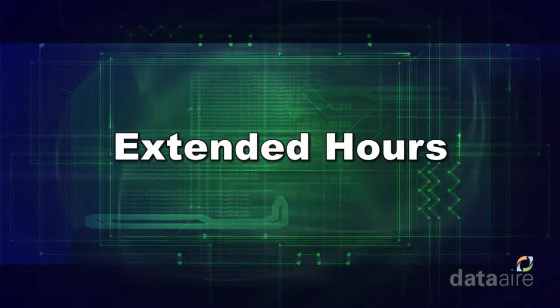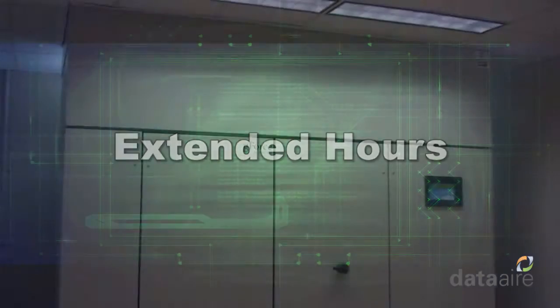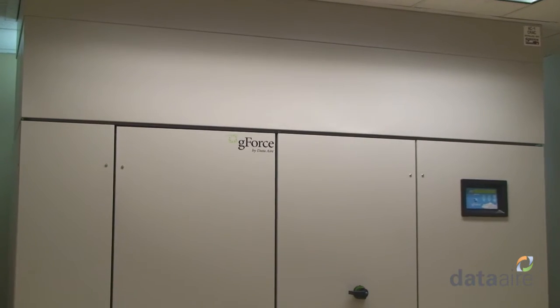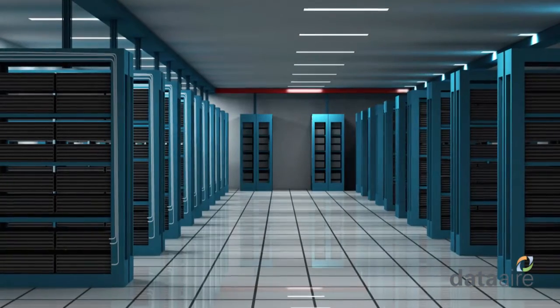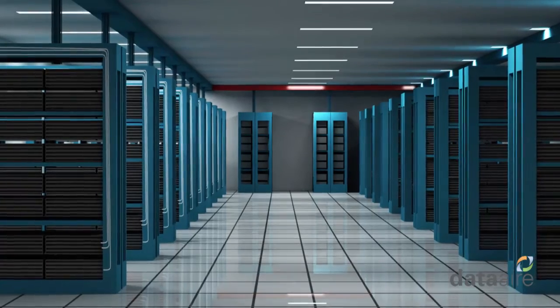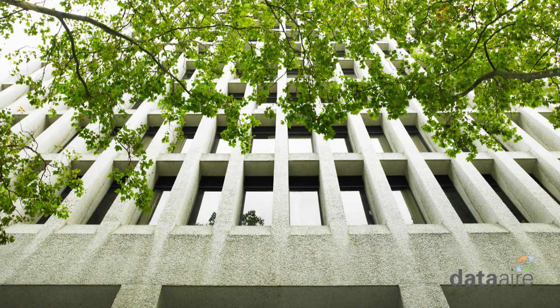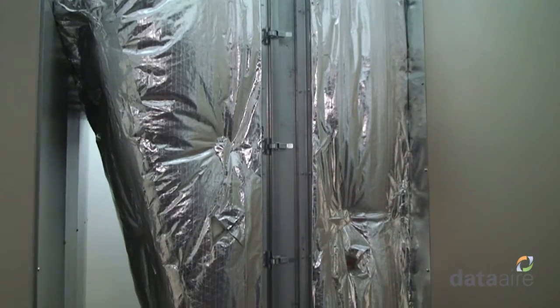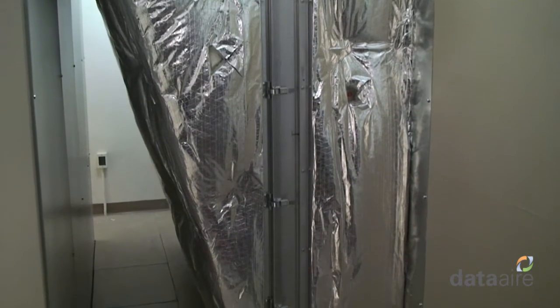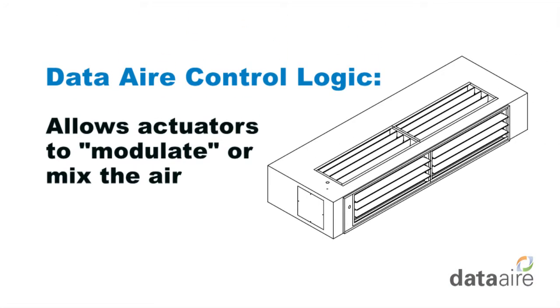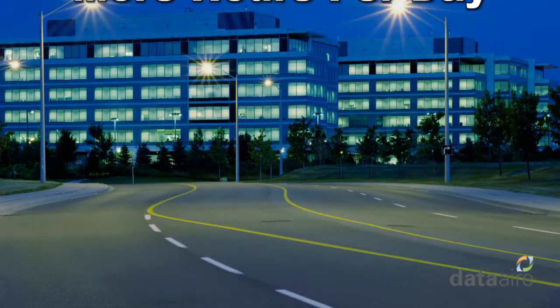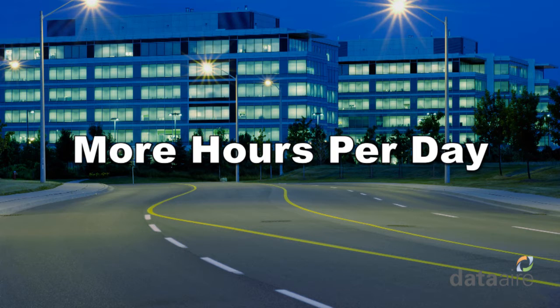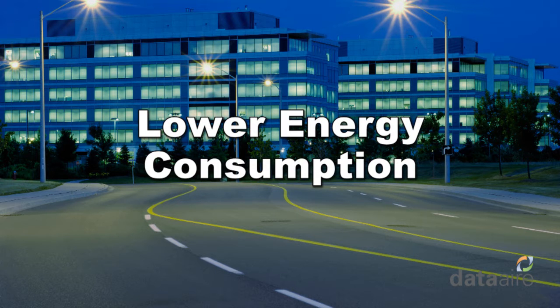Data Aire's control logic permits extended hours of economizer use compared to many competitive units available in the market today. Our control logic continuously measures both temperature and humidity in the data center space and compares that to the temperature and humidity of the outside air. Rather than terminating the use of outside air when it exceeds the set points, Data Aire's logic allows the actuators to modulate or mix the return and outside air. This continues until the conditions in the room reach the limits set by the data center. By doing this, the economizer can be used for more hours per day. The longer the economizer is used, the lower the energy consumption.